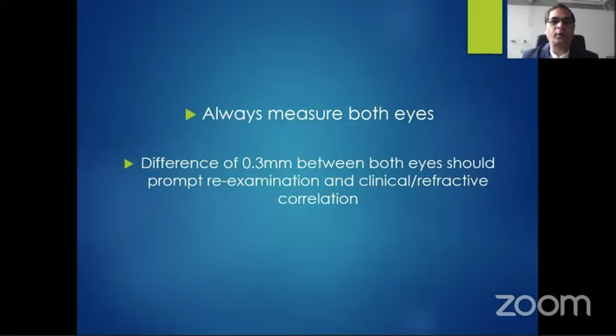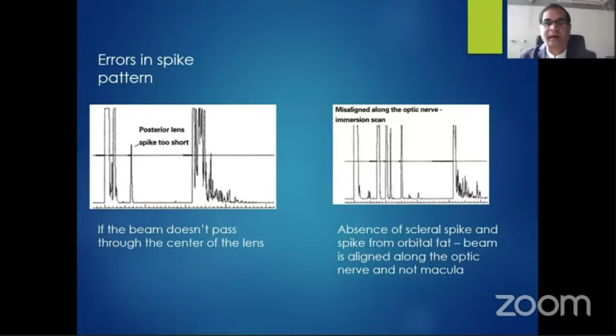Always measure both eyes. A difference of 0.3 millimeter between both eyes should prompt re-examination and clinical and refractive correlation. If the beam does not pass through the center of the lens, the posterior spike will be shorter, and you have to adjust that. Absence of scleral spike and spike from the orbital fat means that the beam is not aligned with the macula, it is aligned with the optic nerve. So you have to move your probe slightly temporally.